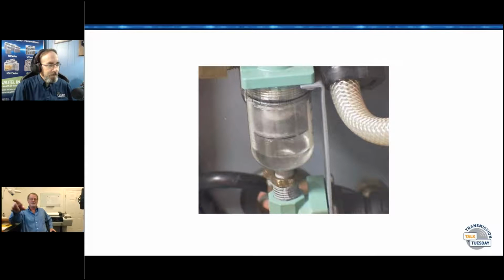With just an adjustment - if you look in the bottom right corner there, you can see the threads - once I adjusted the regulator a little bit, all of a sudden that moisture went away. It took a little while, but it was able to push it backwards during the off cycle and evaporate it. So lots of things can go wrong, but when you see moisture in those, something's wrong somewhere.